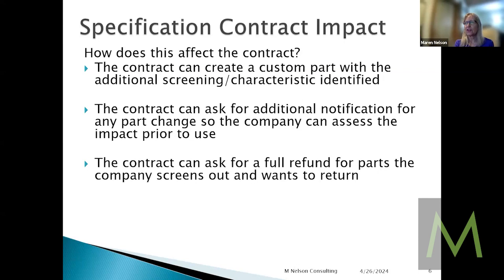That's a different definition. Does a notice of change make it already a custom part? No. Because if you have a product and you have to test it at a test house, the test house may decide that some parts are critical for safe performance, so they put it on the critical component list. And you're not allowed to change anything in a critical component before having consulted with the test house again to say, yes, the change in this critical component is allowed or not.